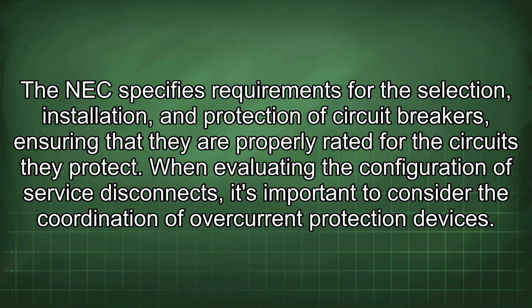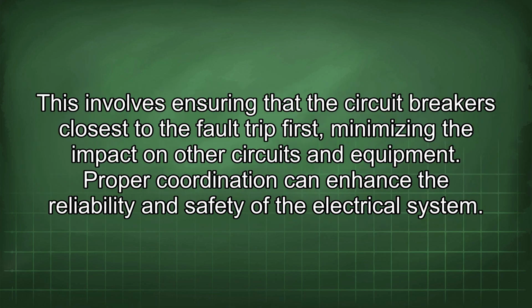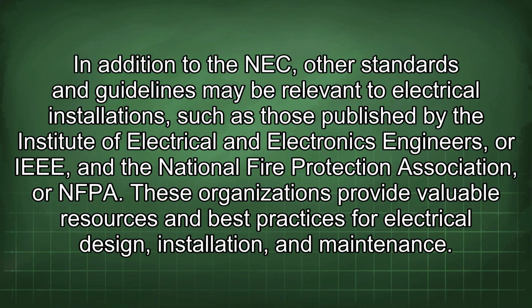When evaluating the configuration of service disconnects, it's important to consider the coordination of overcurrent protection devices. This involves ensuring that the circuit breakers closest to the fault trip first, minimizing the impact on other circuits and equipment. Proper coordination can enhance the reliability and safety of the electrical system. In addition to the NEC, other standards and guidelines may be relevant to electrical installations, such as those published by the Institute of Electrical and Electronics Engineers, or IEEE, and the National Fire Protection Association, or NFPA. These organizations provide valuable resources and best practices for electrical design, installation, and maintenance.